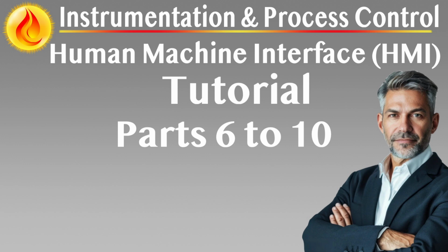HMI console types. Two main types of console configurations are used. Freestanding console: equipment, VDUs, keyboards, pointing devices, is fixed into an enclosed cabinet structure. These offer a traditional appearance but can be less flexible in layout and hardware changes. Desktop or workstation console: displays and peripherals are placed on open desks. This configuration offers greater adaptability, easier maintenance, and is often more cost-effective.